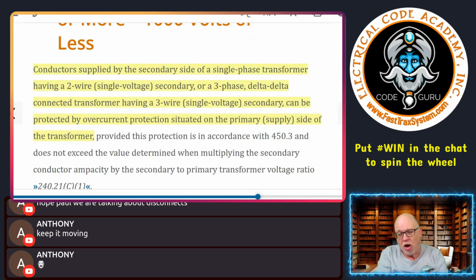There are unique applications where I can have a transformer, and the primary protection for that transformer can not only protect the transformer, but also protect the secondary side of that transformer, provided the type of system that it is. So if you're supplying that transformer with single phase or three phase, and we're dealing with a single voltage, an example of a three phase may be if I'm coming in 480 and coming out with a 208 or something like that.